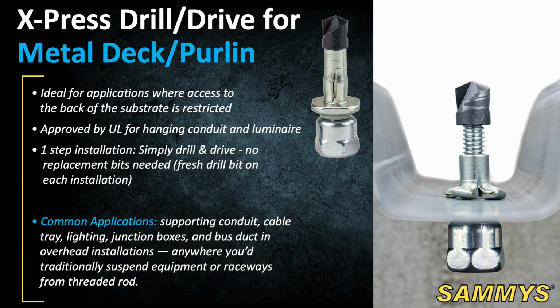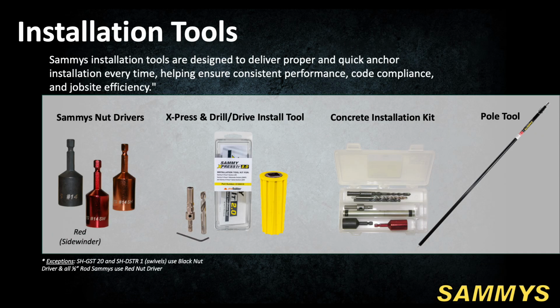This slide introduces the Express Drill/Drive version. Drill/Drive takes the Express concept and makes it even faster. Instead of pre-drilling and then installing, you simply drill and drive in one motion using the dedicated tool. Each anchor comes with a fresh drill bit on the tip. It's UL approved for hanging conduit and luminaires, and it shines on long runs where you're doing dozens or hundreds of similar support points in metal deck or purlins.